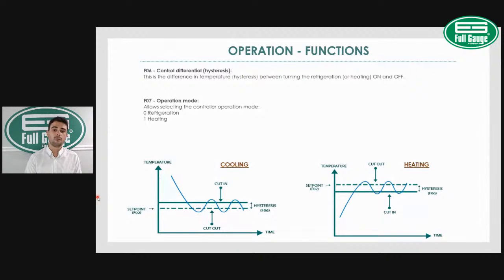So the first thing you have to do is set your cut-in and cutout temperature, your set point and differential. The set point is the cutout temperature. Let's say we want to set the controller to 32 degrees and have a differential of 4 degrees. That means the controller works from 32 to 36 degrees. How are we going to set that? F06 is my differential. Here, I'm going to set this to 4. So F06 set to 4 will provide a 4 degree differential on my cooling system.